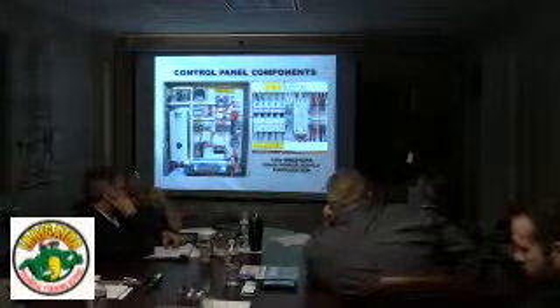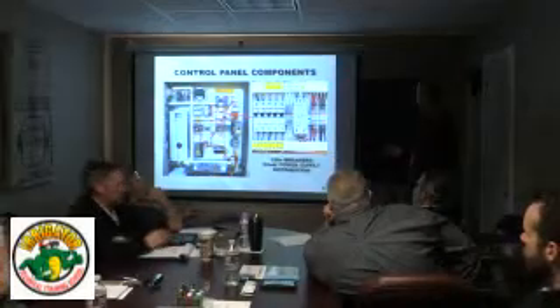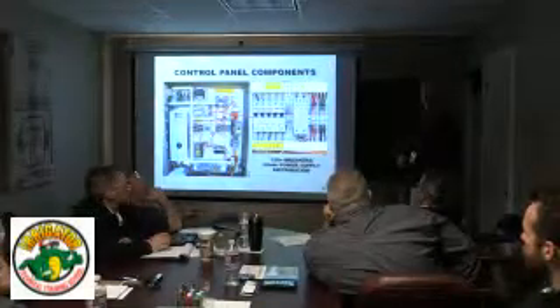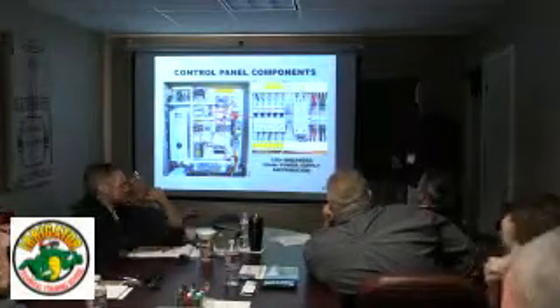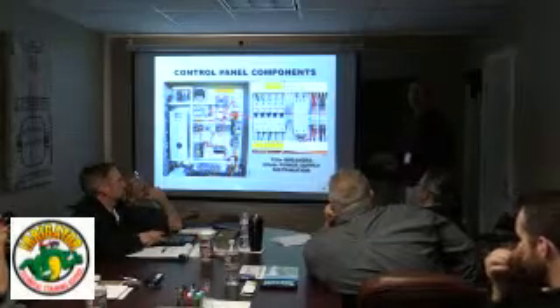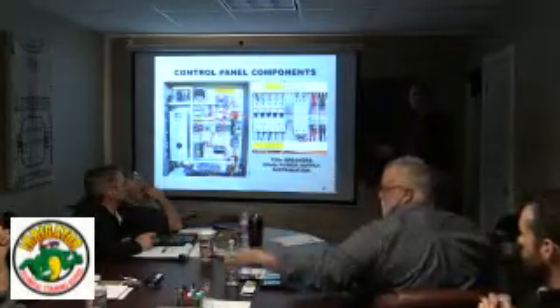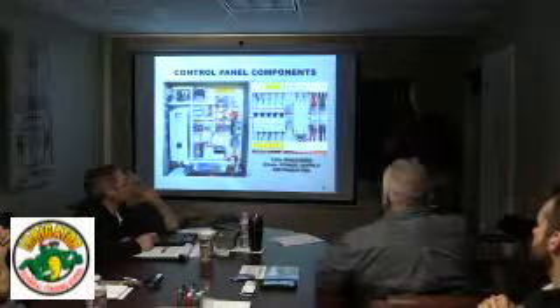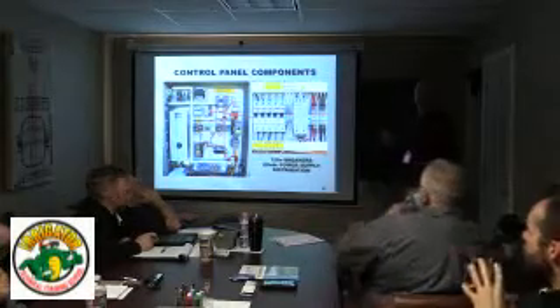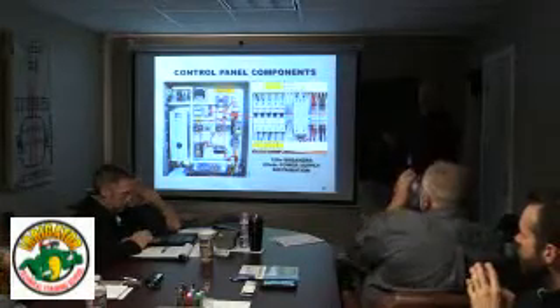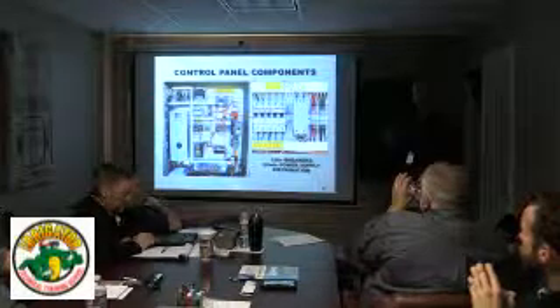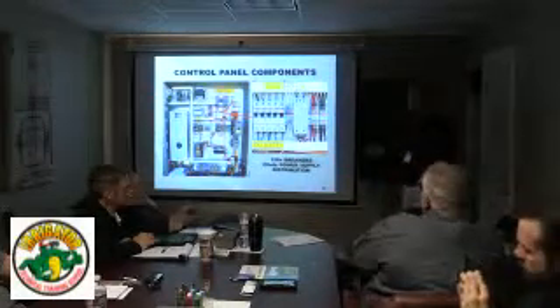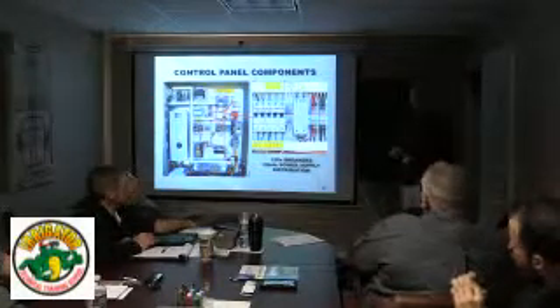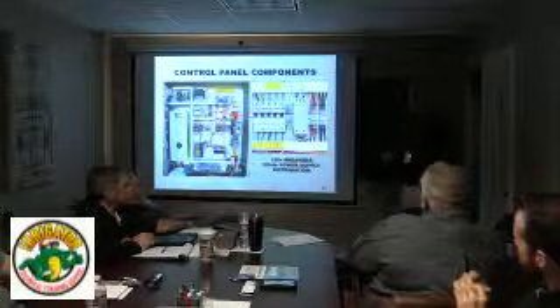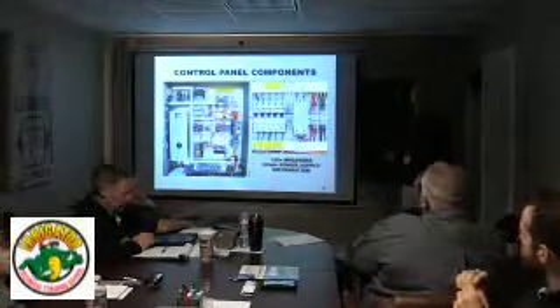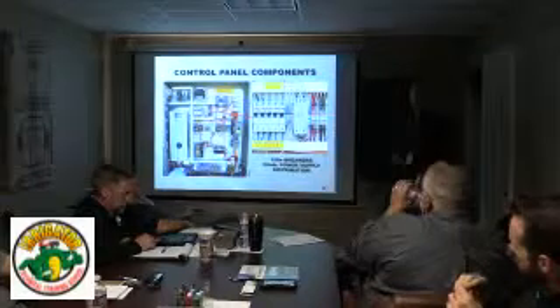First, before you do anything else, pull this red wire out of here and test it again. A lot of cases, you're going to pull that red wire out of there. You're going to see that green LED come back on, and the power supply is going to come back to life. The reason is that these power supplies are short circuit protected. So if you short this output out, it's just going to die, and you're going to measure 0 volts. But it's protecting itself. It's got short circuit protection in it.